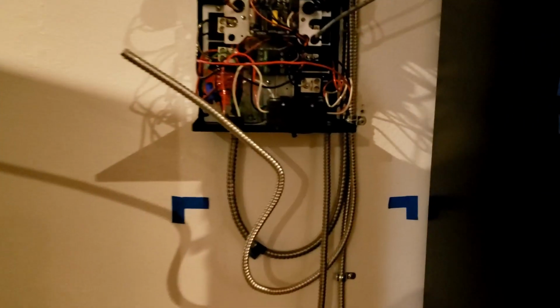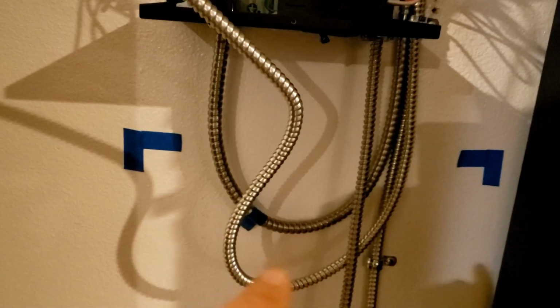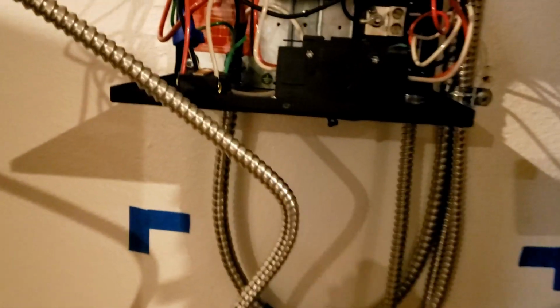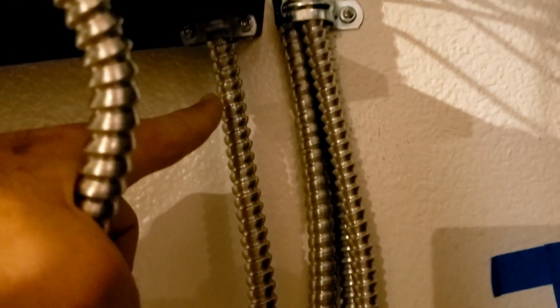So what I decided to do is take this new wire that I brought in to connect to the idler motor and move it across the shop. I determined I can bend this wire into position and get it to go up underneath in replace of the cable currently attached to the motor. I can loop it around and it'll look okay, then go up in there. It's a very simple setup.